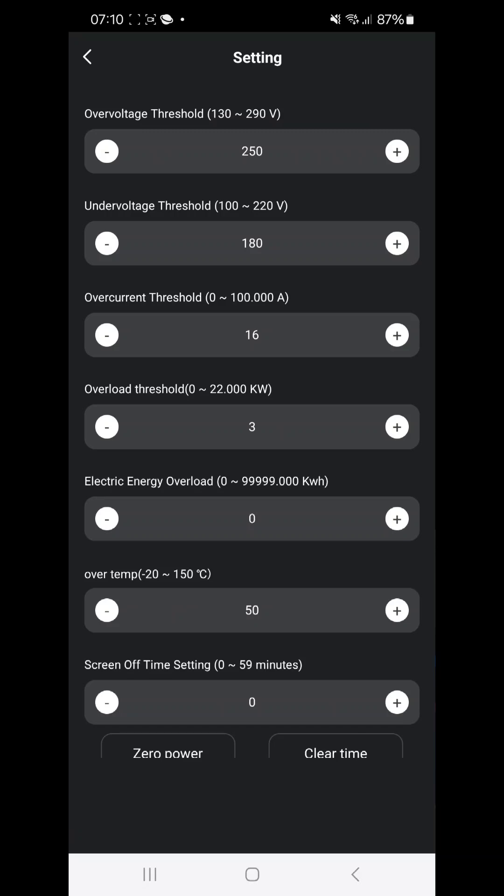Overvoltage threshold is default 250 volts, that's okay for me. Undervoltage is also there. Overcurrent I have set it to 16 ampere, not more than that. So here I can see it says 100 amperes maximum. According to the specification it should be able to do only 63, but interface allows still 100 ampere, so I don't trust that much.